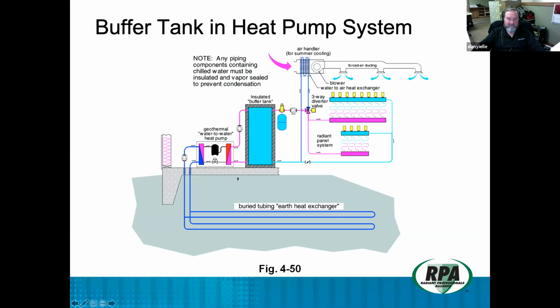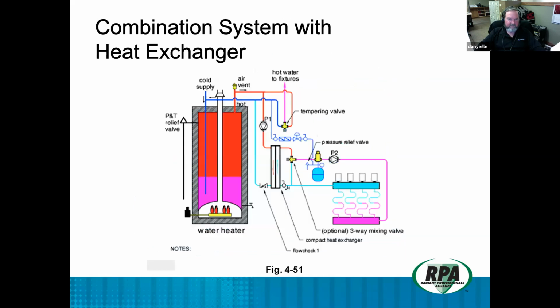But when you don't have a variable speed compressor, you've got to have a buffer tank. The reason for this buffer tank is the hardest thing that you can do to this compressor is to start it. And when you start it, you want it to run for a long time. And when you're done with it, you want it to be off for a long time. And the only way to achieve that is to have basically a large storage tank that when it turns on, it runs for a long time. When it turns off, it stays off for a long time. Well, with variable speed, this goes away. The buffer tank is no longer necessary. The compressor is basically going to vary its speed based on matching demand to the load. So hopefully those folks have gotten it together and we'll be out with something real soon.